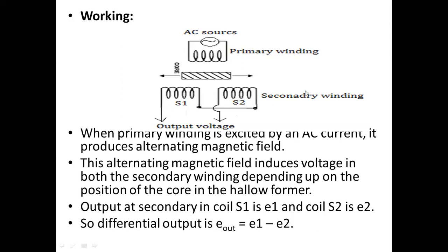That is called the linearly variable differential transformer. Differential means we use two transformer secondary windings, comparing and differentiating between these two. The difference between these two gives the displacement in the form of voltage.